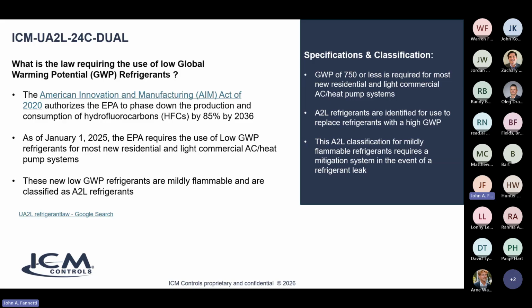So what's the law regarding these low global warming potential refrigerants? Well, the American Innovation and Manufacturing Act, AIM, authorizes the EPA to phase down the production and consumption of all hydrofluorocarbons, HFCs, like the old R22, which is pretty much long gone now. But there are still a few systems around with those, but more like now even the 410A and the old 134, they just get too high of a global warming potential. As you can see, the global warming potential has to be 750 or less for most new residential and light commercial AC units. So unfortunately, those older refrigerants no longer qualify, so the EPA is phasing them down.